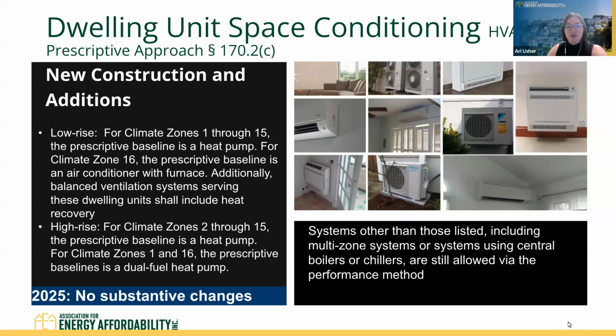You don't have a separate option for a gas space heating system. There's a few small exceptions. So for low-rise buildings, and this is buildings 1 to 3 stories, the prescriptive baseline is a heat pump in climate zones 1 through 15. And only for climate zone 16, the prescriptive baseline is an air conditioner with a furnace. Another feature of the prescriptive requirements is that if you do have a balanced ventilation system, then you will need to also have heat recovery ventilation as well.